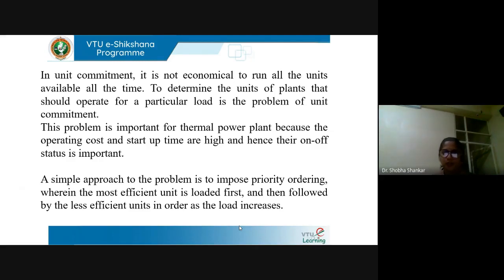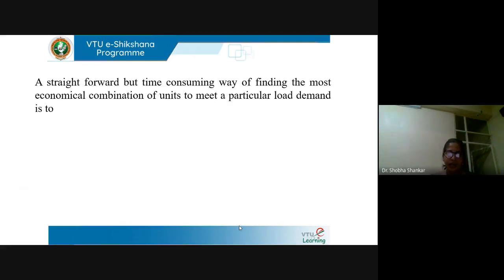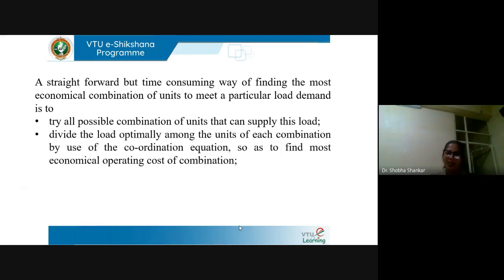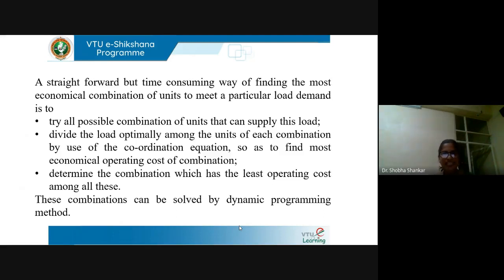A simple approach to the problem is to impose priority ordering, wherein the most efficient unit is loaded first and then followed by the less efficient units in order as the load increases. A straightforward but time-consuming way of finding the most economical combination of units is to try all possible combinations that can supply the specified load and divide the load optimally among the units of each combination by the use of economic dispatch, then determine the combination which has the least operating cost. These combinations can be solved by the use of dynamic programming.